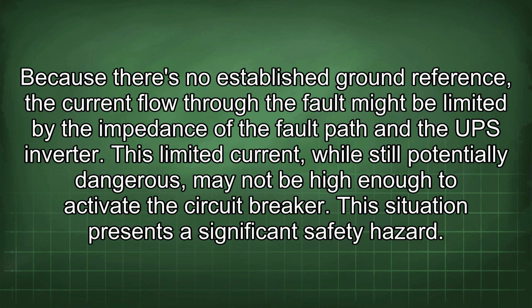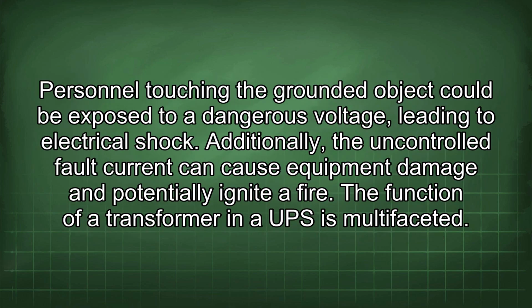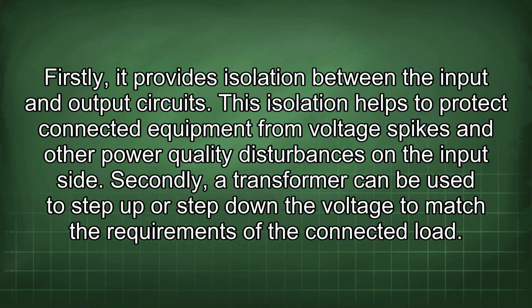This situation presents a significant safety hazard. Personnel touching the grounded object could be exposed to a dangerous voltage, leading to electrical shock. Additionally, the uncontrolled fault current can cause equipment damage and potentially ignite a fire. The function of a transformer in a UPS is multifaceted. Firstly, it provides isolation between the input and output circuits. This isolation helps to protect connected equipment from voltage spikes and other power quality disturbances on the input side.